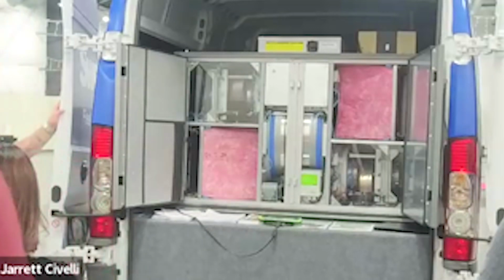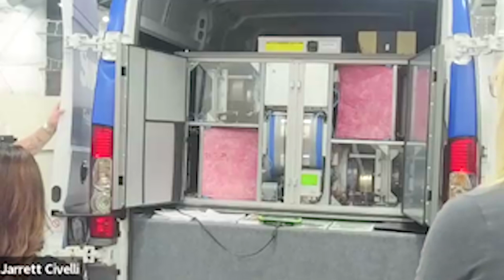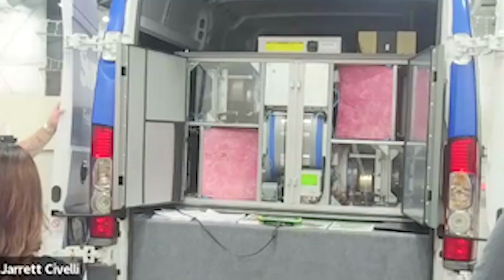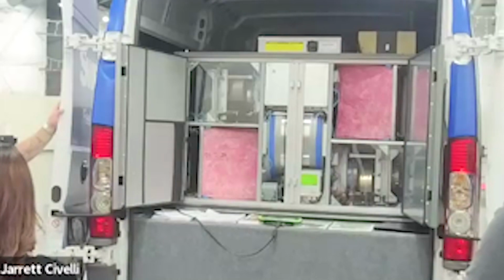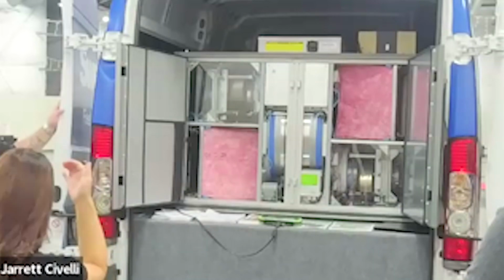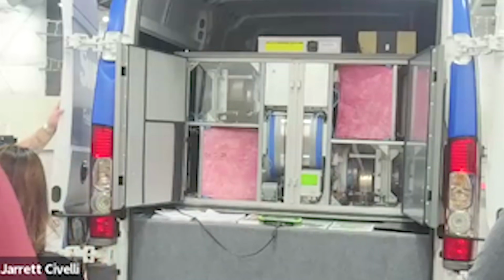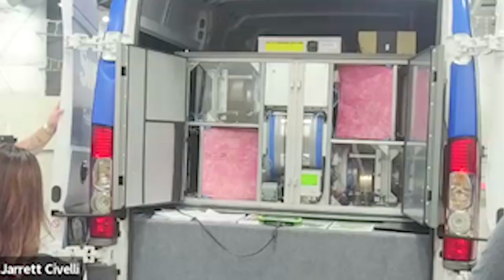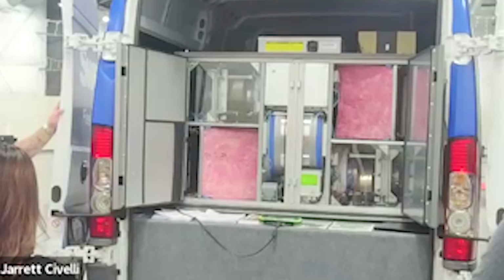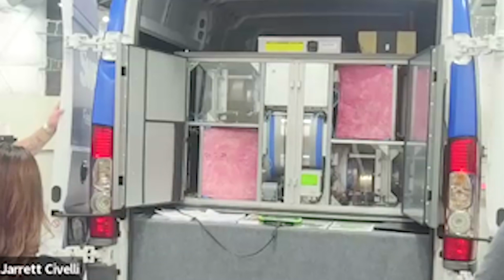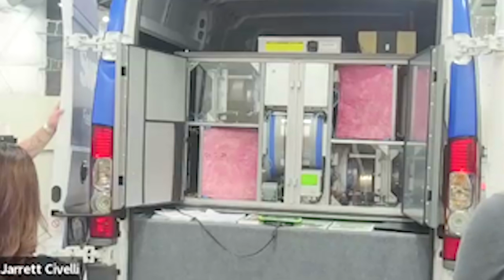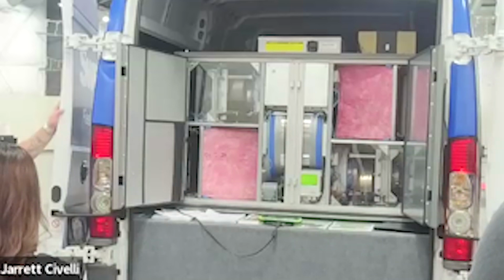That same thing adds to the energy efficiency, because the maintenance personnel know in real time when it's time to change the filters, as opposed to doing it on a cycle. One unit doesn't necessarily need a filter change every 3 months, but another one might need it every month. I don't know how much you guys know, but the old gold standard was just a basic differential pressure switch, and you assume the filter has 0.5 inch of pressure drop initially, and you add 1 inch of water column to that. So you set it at 1.5 inches across the filter, and it's a manual reset thing that just sends an alarm, saying, hey, it's time to come take a look. So it's a neat feature.